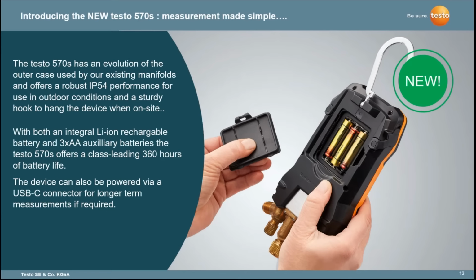And if you have both the lithium ion fully charged and the 3 AA batteries installed, we actually offer a class leading performance of 360 hours continuous use. You can also power the device long term via the USB-C connector. And the reason we've got this long battery life and the option of USB-C direct power is because the 570s is the first manifold we've got in our range that will allow on-site data logging. So where you're needing to leave it on site for an extended period of time, this is why we've got the ability for the instrument to run long-term on batteries or an external power device.